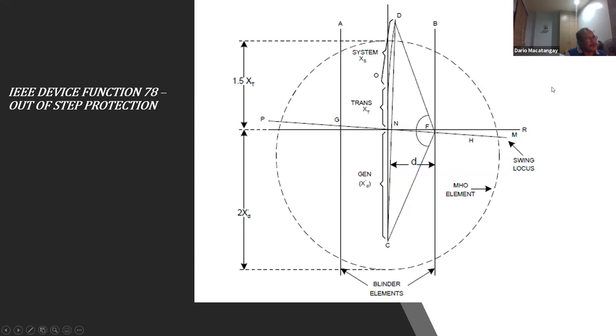The problem is that if the fault is not interrupted, you can lose synchronism between the stator and the rotor, and when you lose synchronism you have to trip the generator for out of step. This type of protection typically has dual blinder elements, and this is your Mho type. Once there's a fault in the system that causes a swing, the impedance will travel inside here. Once it gets to the first blinder, if it's a stable swing, it comes back out, so it's not going to trip. If the impedance crosses the first blinder and traverses the second blinder, then it's considered an unstable swing, and it should trip the generator. So that's your out of step: unstable crosses here, stable comes back.